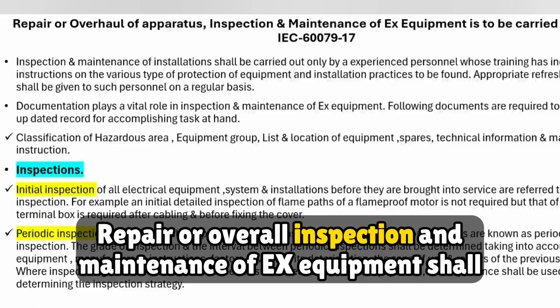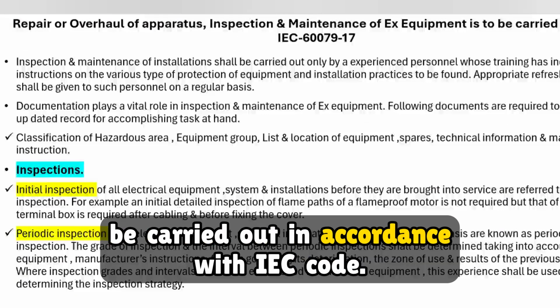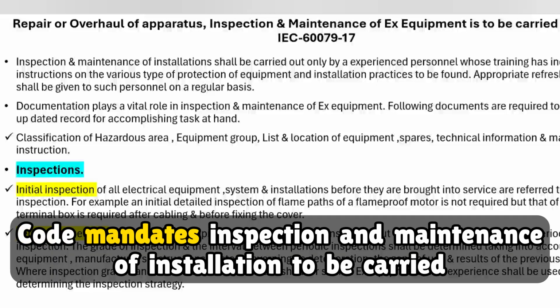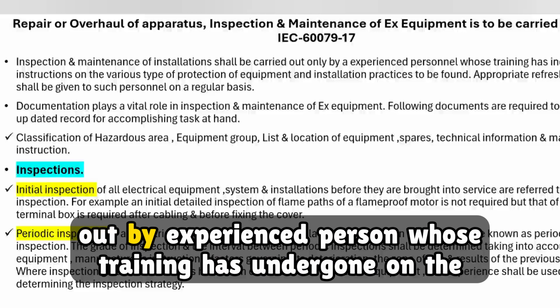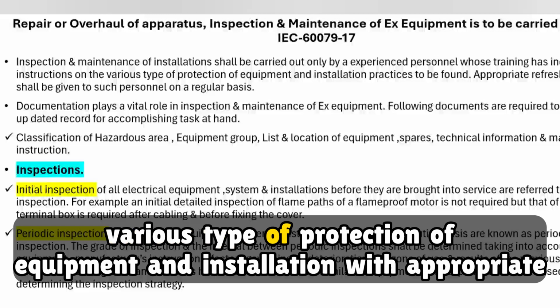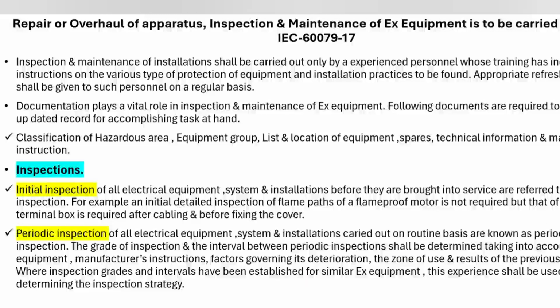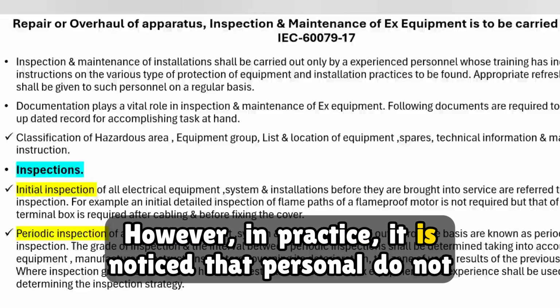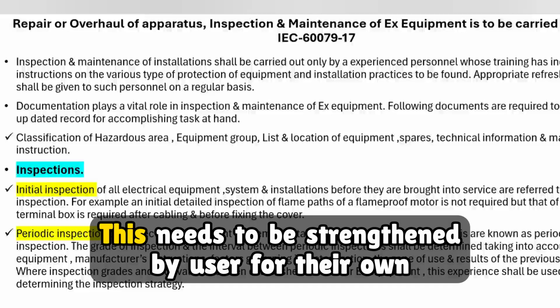Repair or overhaul, inspection and maintenance of EX equipment shall be carried out in accordance with the IEC code. The code mandates inspection and maintenance of installation to be carried out by experienced personnel whose training has covered the various types of protection of equipment and installation, with appropriate refresher training. However, in practice, it is noticed that personnel do not undergo any training. This needs to be strengthened by users for their own safety.